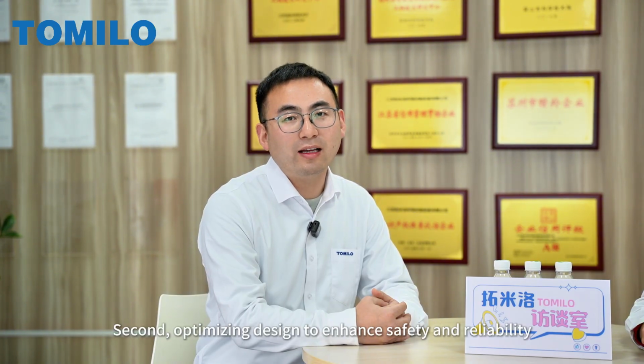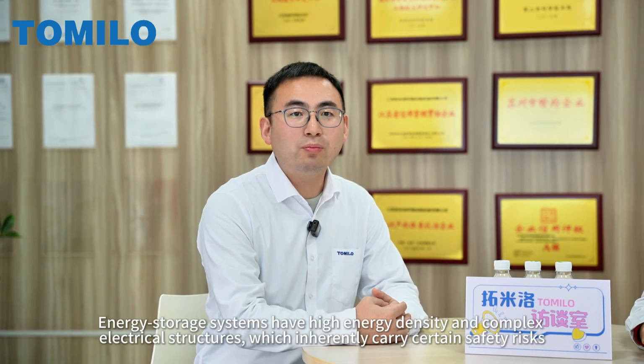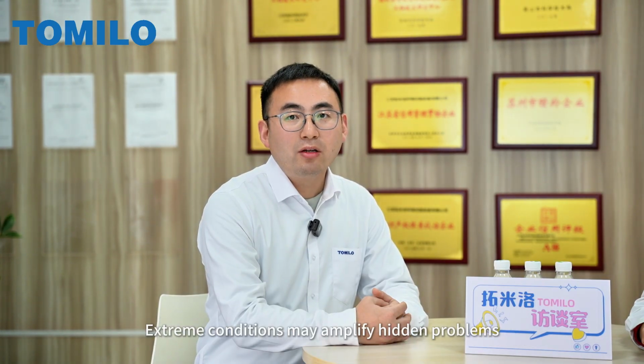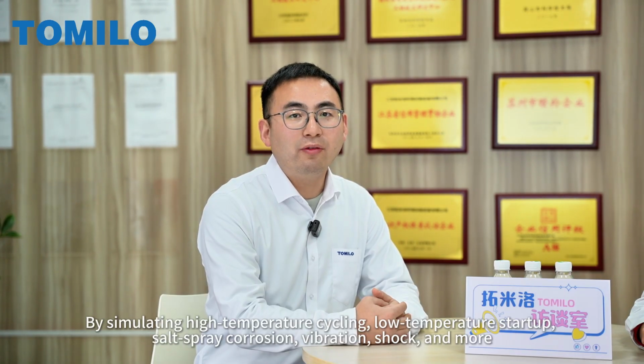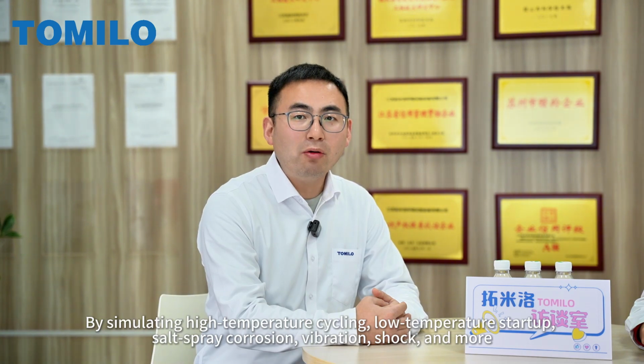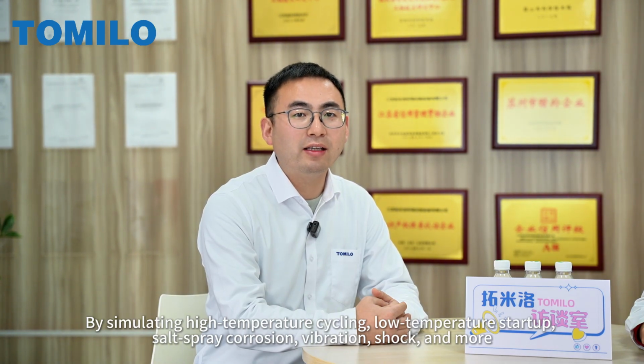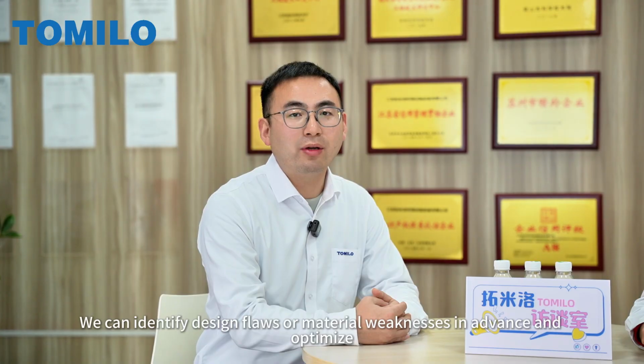Second, optimizing design to enhance safety and reliability. Energy storage systems have high energy density and complex electrical structures, which inherently carry certain safety risks. Extreme conditions may amplify hidden problems. By simulating high-temperature cycling, low-temperature startup, salt spray corrosion, vibration, shock, and more, we can identify design flaws or material weaknesses in advance and optimize thermal management structures, sealing designs, and anti-vibration components to reduce safety risks.